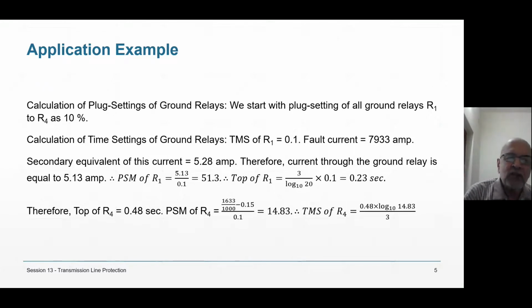For 7933 amperes, the equivalent secondary current divided by 1500 gives me 5.28 minus 0.15, where 0.05 is the excitation current, 3 times 0.05. So that gives me 5.13. 5.13 divided by 0.1 plug setting gives 51.3, which I cannot take. So the time of operation is 3 upon log 10 20 into 0.1, which I assume is 0.23 second.